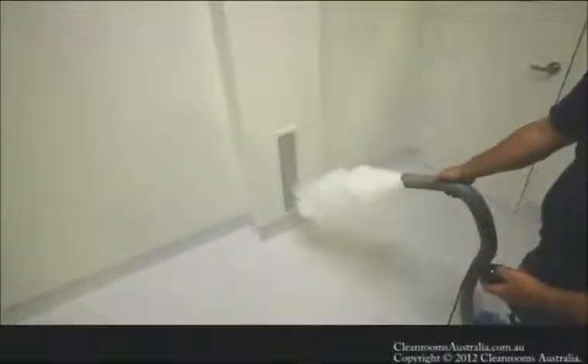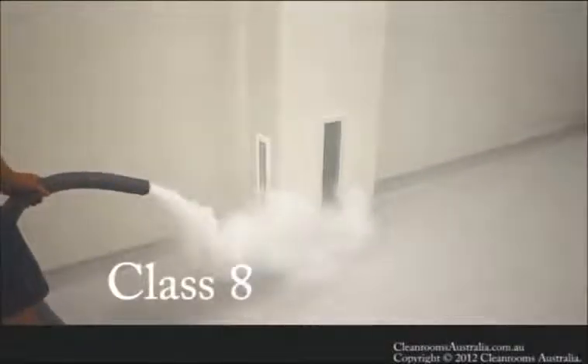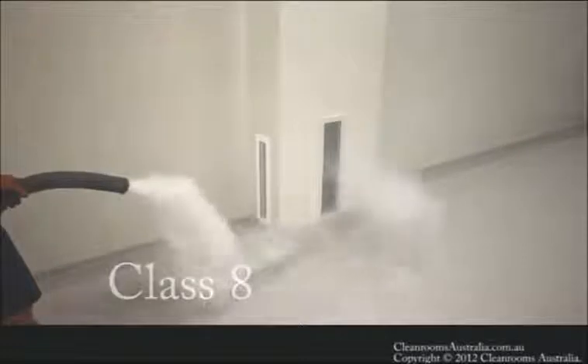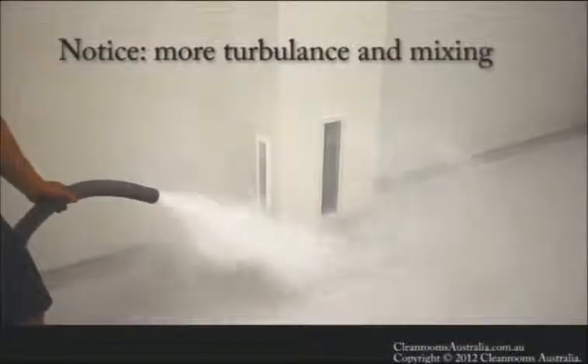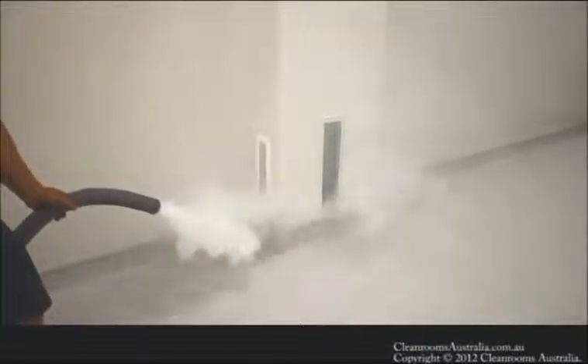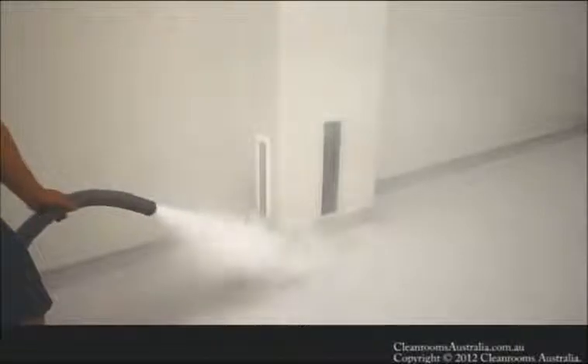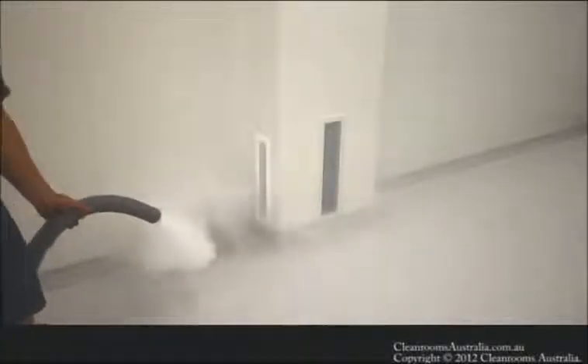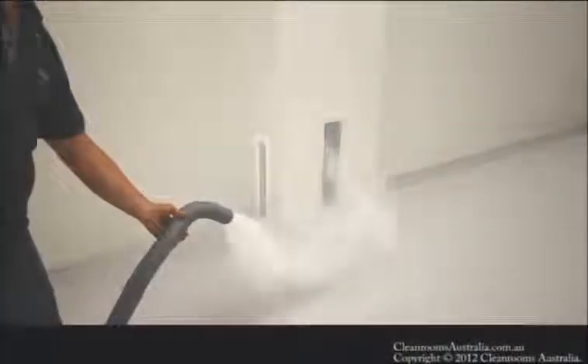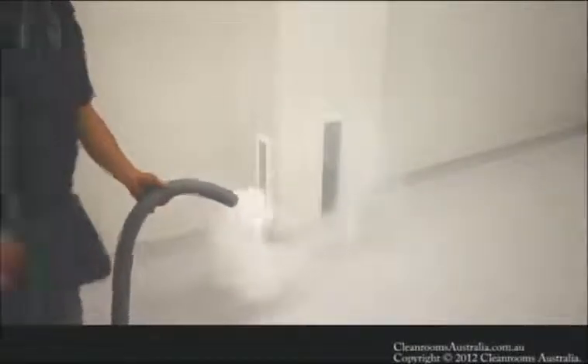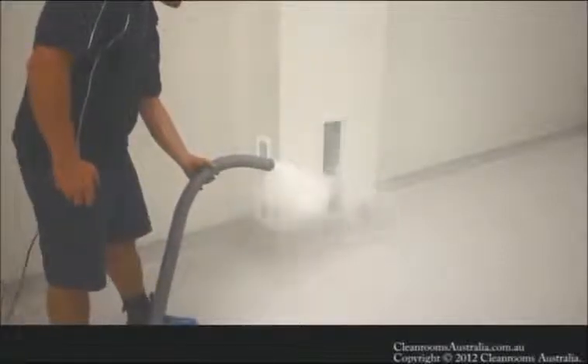As you're only going to be doing this on one or two occasions to prove your mixed flow or laminar flow, we take the opportunity at the commissioning stage while technicians are still able to get into the cleanroom without gowning, as the smoke is likely to contaminate the entire facility. If you don't get a take within one or two shots in a mixed flow area, the smoke will disseminate across the cleanroom and you won't be able to get the shot very well.